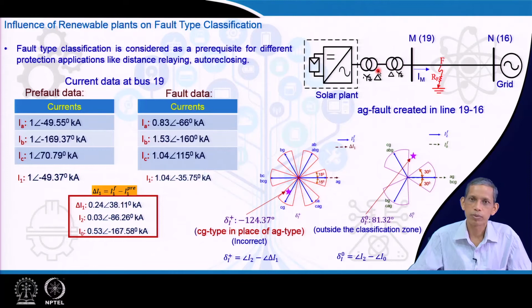Now, we will try to analyze this. This current angle based fault classification logic, if you remember, started with the associated fault current passing through the faulted path and the corresponding network positive sequence, negative sequence and zero sequence. For a phase A to ground fault, they are in series with 3 RF, and this faulted path current, the positive, zero and negative sequence, align at certain angles. The sequence network for the faulted path current reveals different angles for different types of fault.